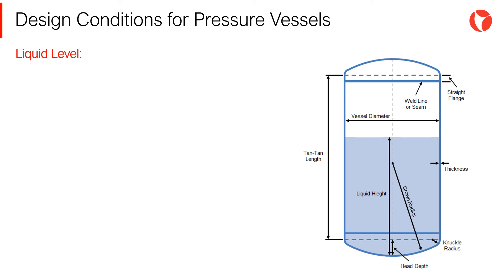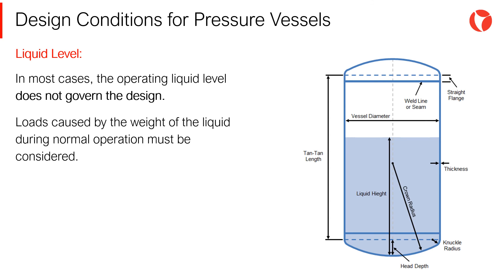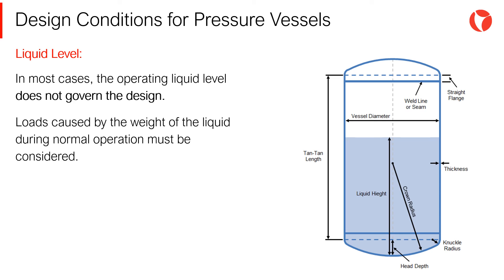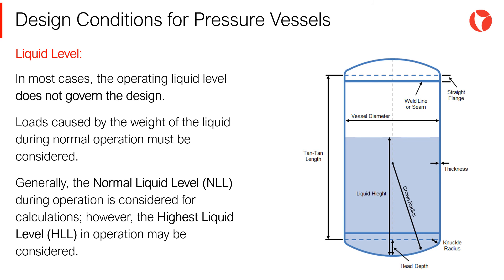In most cases, the operating liquid level does not govern the design. Still, especially for large horizontal vessels, the loads caused by the weight of the liquid during normal operation must be considered. Generally, the normal liquid level (NLL) during operation is used for calculations. However, from a conservative point of view, the highest liquid level (HLL) is sometimes considered.